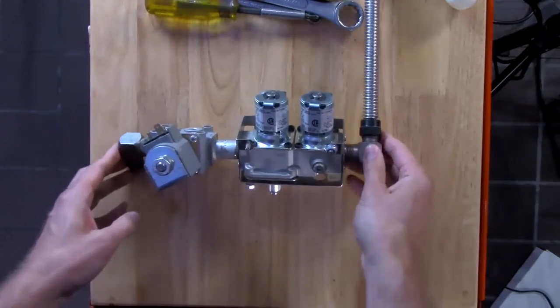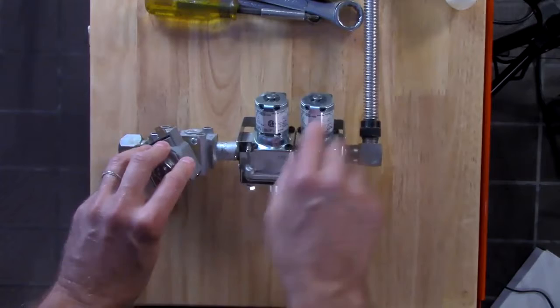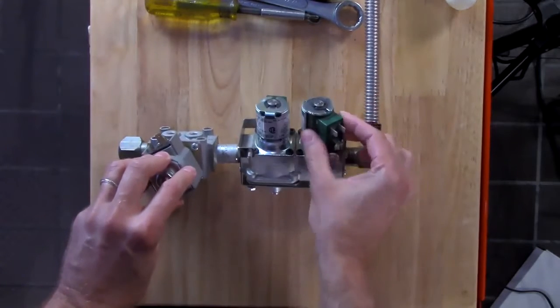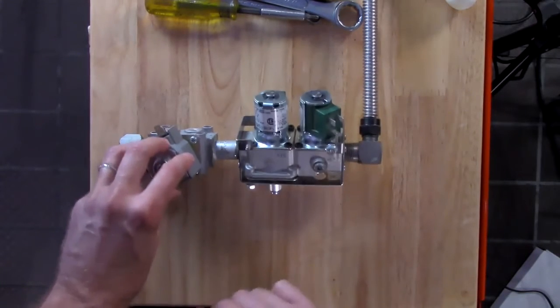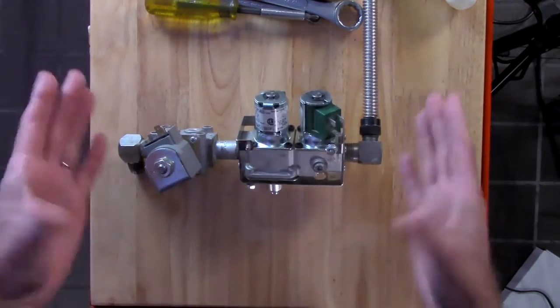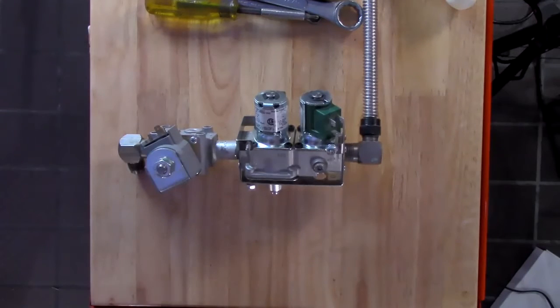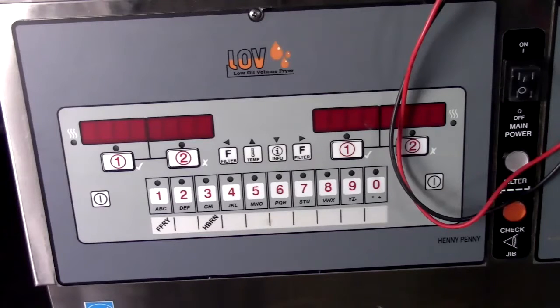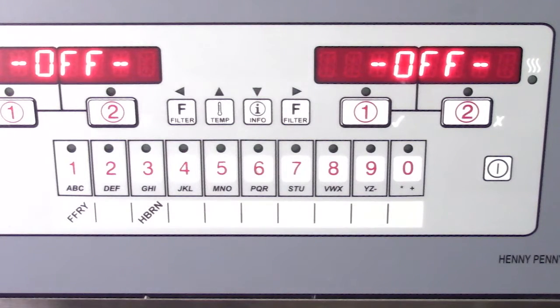You could possibly need just the gas valve coil. Okay, so it could just need the gas valve coil, and potentially you might need to bring out a control board. You want to make sure you take a control board just in case, in the event that it's not sending the voltage on from the ignition module out to the gas valve.